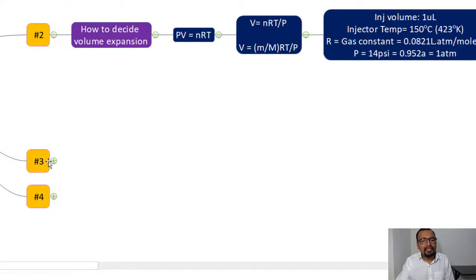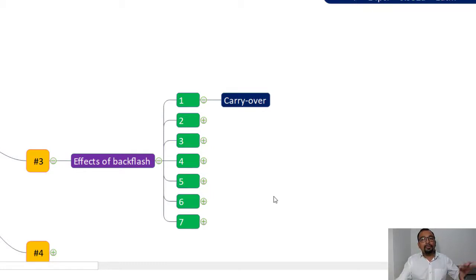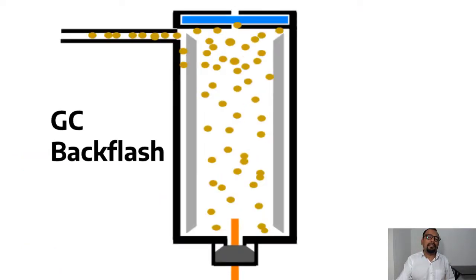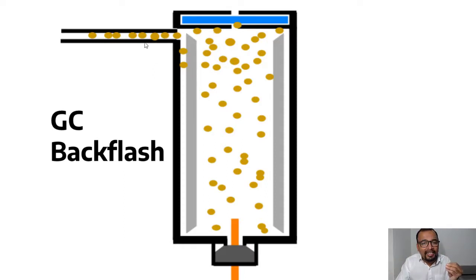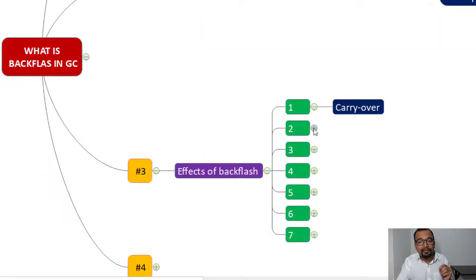Let us understand the effects of back flash — there are seven different effects to discuss. The first is carryover. When the sample accumulates in the carrier gas inlet line — a low-temperature area — it condenses there. When you inject the next blank injection, this condensed sample re-enters the injector port and column, producing a response even from a blank injection. This is carryover caused by back flash.